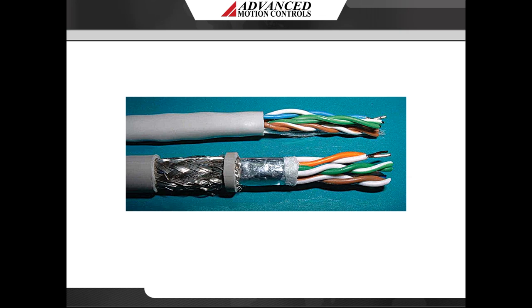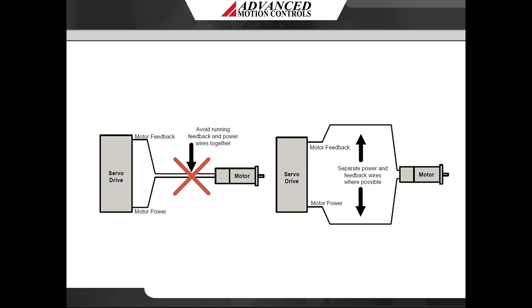Use of a twisted shielded pair for the feedback wires is recommended. Ground the shield at one and only one point — the drive chassis ground. The motor power wires are a considerable source of noise and the feedback wires are susceptible to receiving it. Placing signal cables next to power cables can allow PWM switching noise to couple from power lines onto the adjacent signal lines. To avoid this, route the motor power wires and motor feedback wires in separate cable bundles and far apart. As the distance between the lines increases, the effect of inductive coupling is reduced.